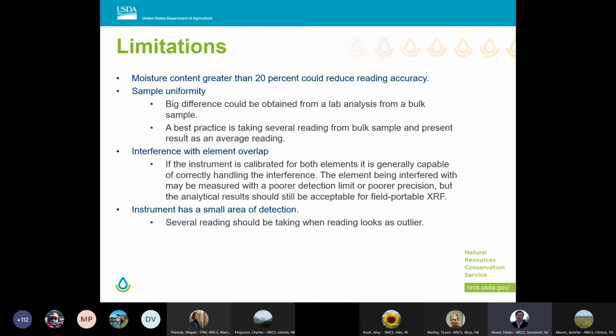And as I mentioned before, the instrument has a small detection area. So you have to keep looking at your data during collection, because if you find an outlier, you should retake another reading, because maybe your reading is being taken on a small chip of, for example, paint in the soil, and then your readings are not going to be accurate.